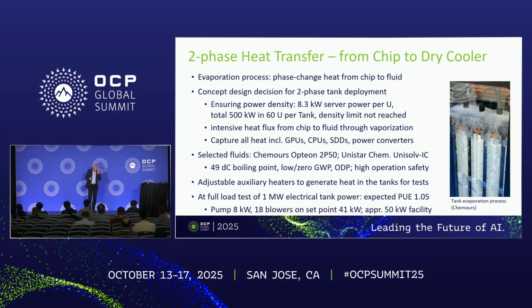This comes together with about 2 pumps, one running at about 8 kilowatts. Then we have 18 blowers on top, altogether doing about 40 kilowatts, so 50 kilowatt parasitics over 1 megawatt of IT would be 5%. That's the goal.